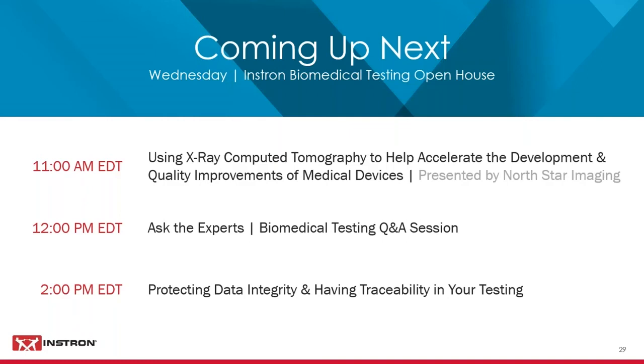So we have another question relating to transducer calibration and how it ties into IQOQ. Transducer calibrations or verifications are a separate service that Instron provides, where a field service engineer checks your load cells, extensometers, and other transducers against a known standard and makes sure the results are accurate to the degree they're assigned to be. Those services are always quoted separate from IQOQ, but the verification certificates are referenced in the IQOQ as they tie together to the complete Instron validation package.